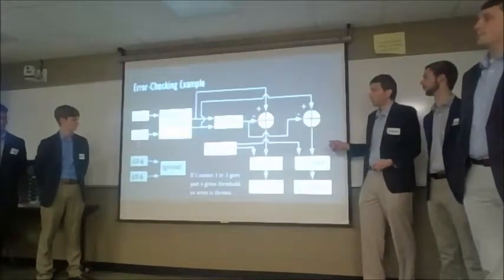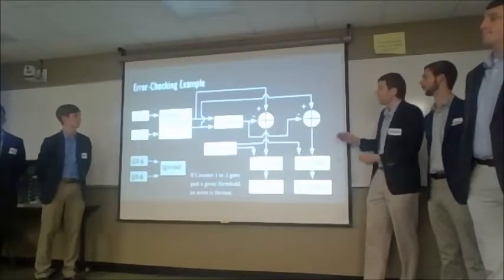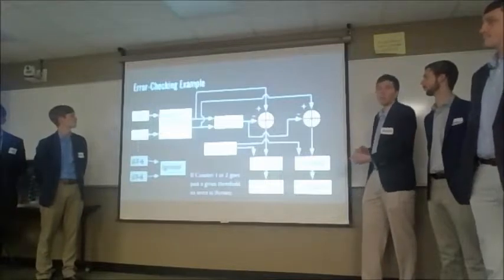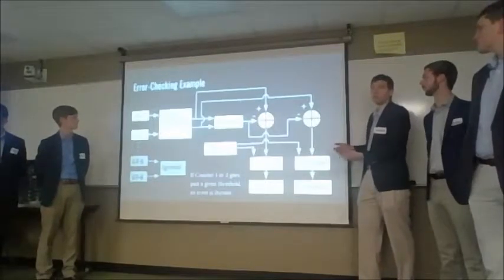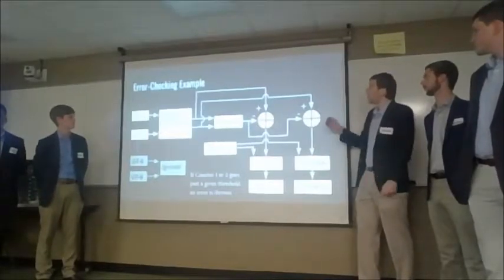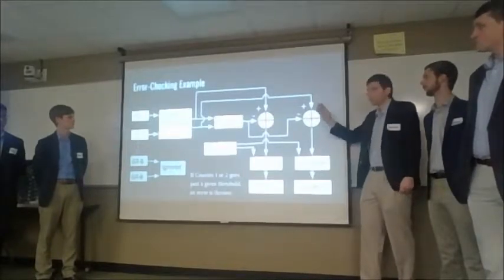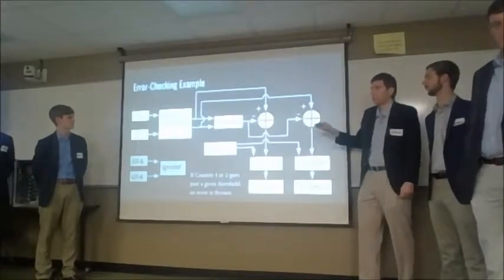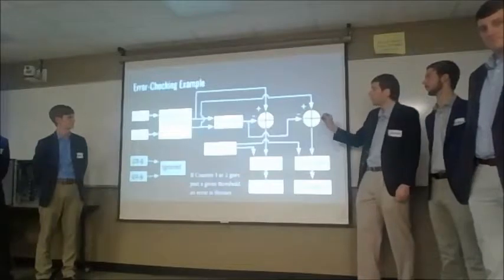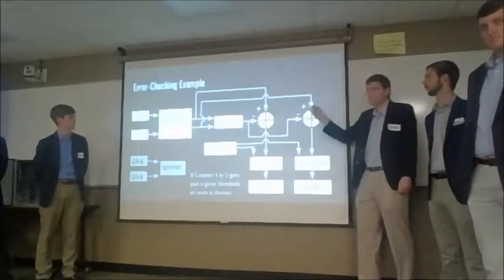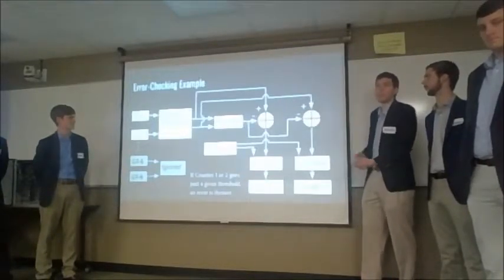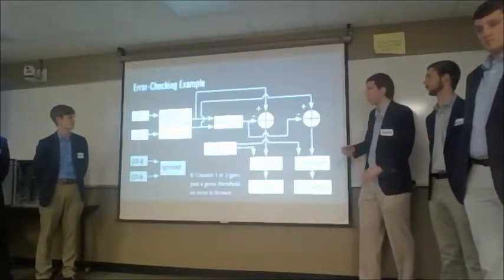This is an example of trying to find an error. In this example, we're trying to find out if one of our solar panels is underproducing, producing less than the others. Here panels 1 and 2 are on, the rest are deactivated, so their values are ignored. The values are in CT1 and CT2, where CT stands for current transducer.